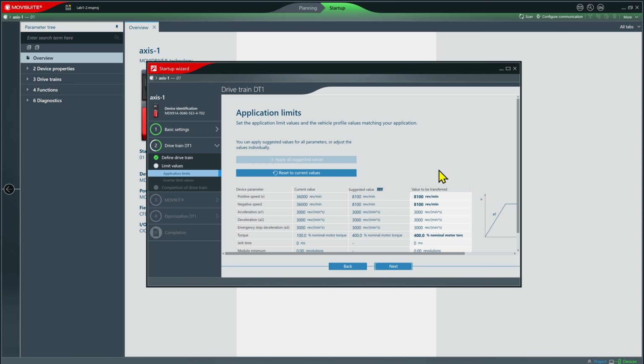Now it's going to let me set my application limits. Remember, I set these to the motor's nominal speed, so I'm going to go in here and do this again. Set it to 4,500 RPM in both directions. I'm going to set my acceleration and deceleration values to 9,000 RPM per second. And I've got an emergency stop value, which I really should set as well, and I should never have this slower than the regular acceleration and deceleration. So I'm going to set this to 9,000 as well. I can leave all the other settings alone, so I'm going to click Next.